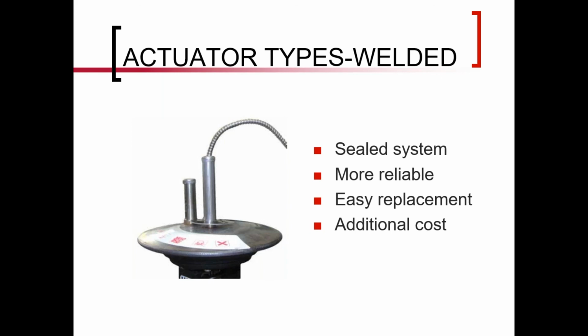So this type doesn't have a bellows, just has a diaphragm internally, and the diaphragm is captured in between the two actuator plates, and it's welded closed. So it is a true sealed system, typically more reliable, and it's also easy to replace. But usually a little bit more costly because there's more material involved, and there's welding and things like that. So like so many things, it's probably going to be more reliable, so you're paying a little bit more for it.